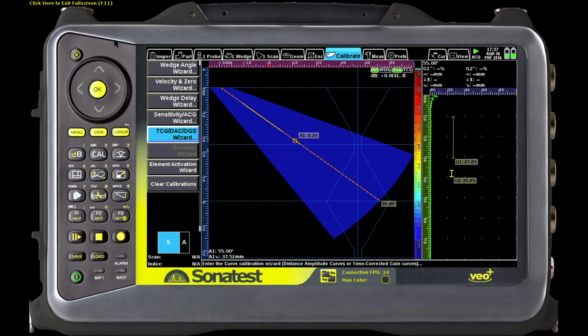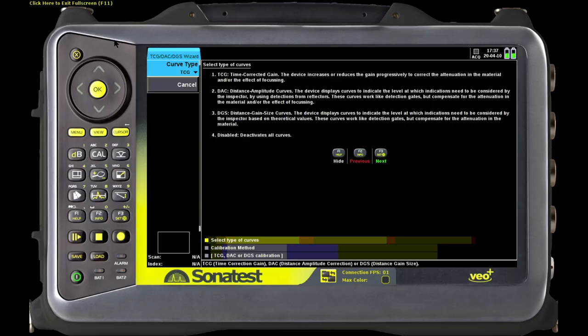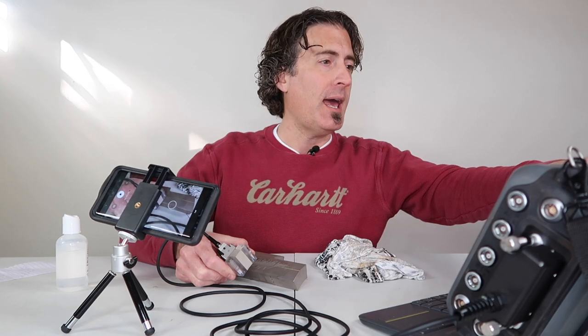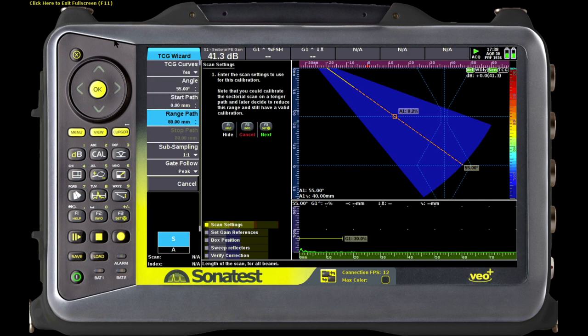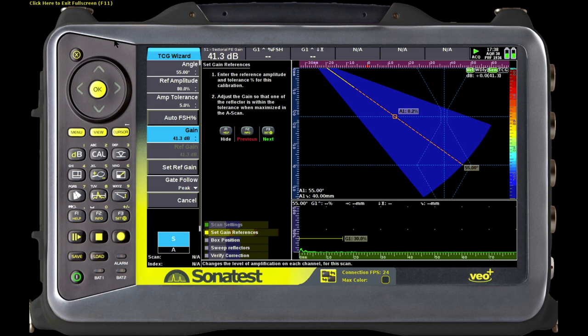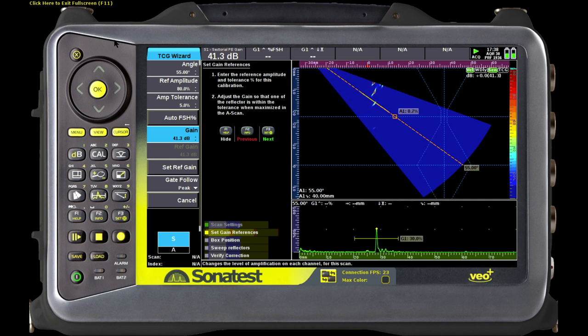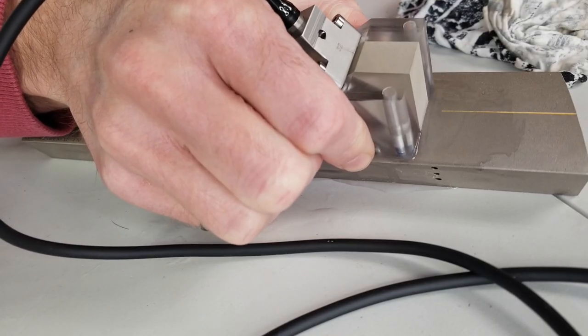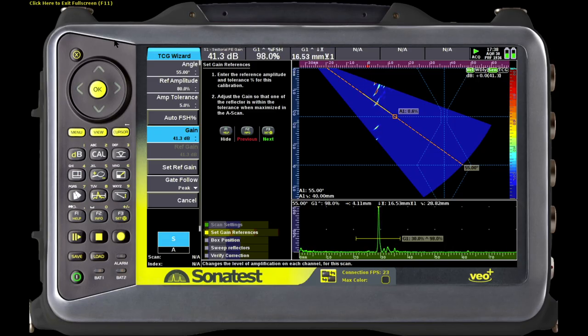Now we're going to get to the good stuff and do our TCG. We're going to go into the wizard and calibrate scan one on an OmniScan — that would be group one. Curve type is TCG, not a DAC, and the calibration mode is automated. You can do a manual TCG if you like. The start path and range path are the same as what I had before. The reference amplitude will be 80 plus or minus 5 percent, and then there's a gain setting here we use just to ensure that the first reference reflector, which should be the loudest one, is at about 80 percent.